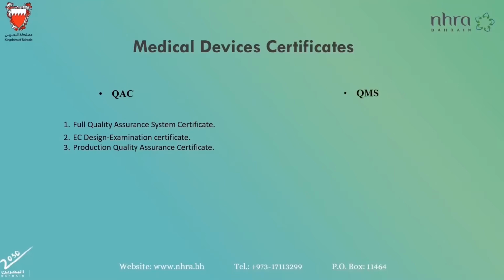Moving on to the QMS. NHRA accepts only the ISO 13485 and the new MDR and IVDR certificate if they are recognized by the NANDO. To those who are not aware of the new MDR and IVDR certificates, in summary, those new certificates are a merge between the EC and Quality Management System requirements, which is more comprehensive and detailed compared to the MDD.